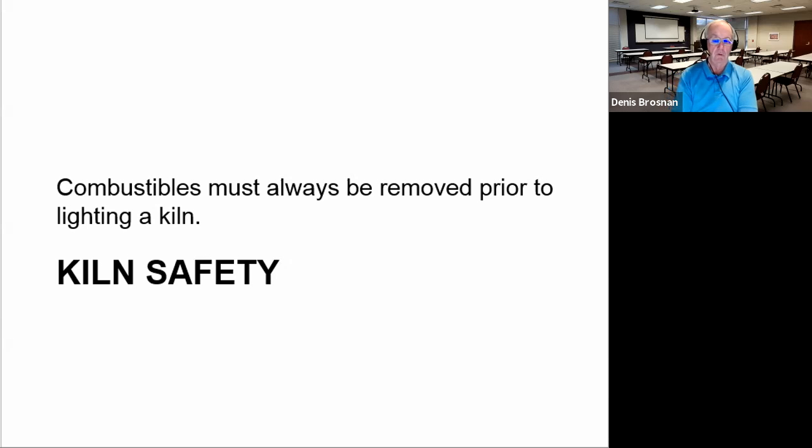It's not easy to do with a tunnel kiln, a lot of burners to make sure are functioning properly. And so when they got to the last kiln, it was getting late in the day, and I suppose people were tired. In the preheat section of the kiln, there were some burners where the safety system was not functional.